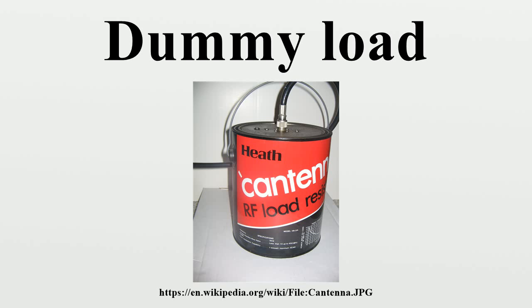There are also dummy loads for power supplies, known as load banks. These may be used, for example, for factory and in-service testing of standby generators. A load bank may be used to stabilize a power system in case of loss of load, for example, on an isolated wind or mini hydro plant.